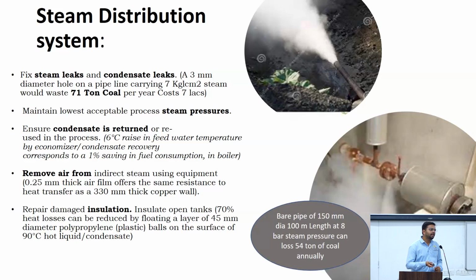So the leakages are not so small that we can neglect them, because a 3 mm diameter leakage at 7 kg pressure in the steam line can cause a loss of 71 tons of coal equivalent annually. So this is a very significant leakage that we cannot neglect. In some industries we are seeing that they are negligent about leakages.